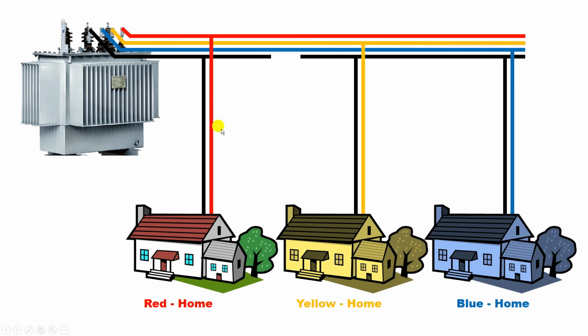It means to this house, phase supply and neutral supply is proper, but the neutral power supply for these two houses got broken. If neutral power supply breaks at this point, then this house and this house will both be connected in series.